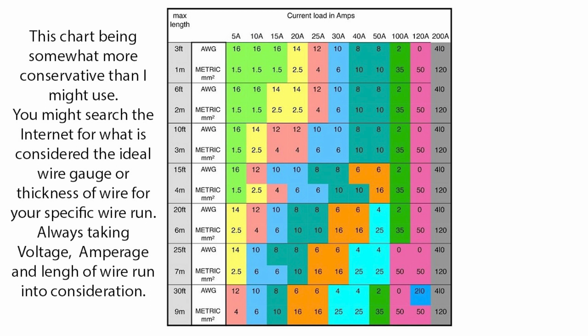I could actually go up as far as a 240 amp circuit breaker. However, I personally like to stay a little lower than my maxed out inverter in the way of cable wire gauge or thickness running from my 100 amp battery to my 1000 watt inverter. I use AWG2 or 35mm squared. That is 35 millimeter squared, represented by 35 mm and the number 2 cable wire, which is rated at 260 amps. That being as long as the run of cable wire is less than 6 feet or 2 meters in length. We don't want the wires melting if there is a problem.